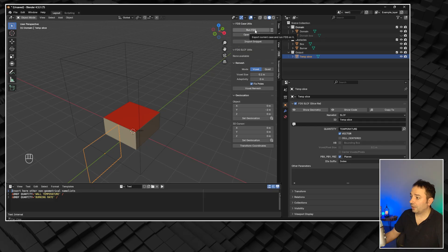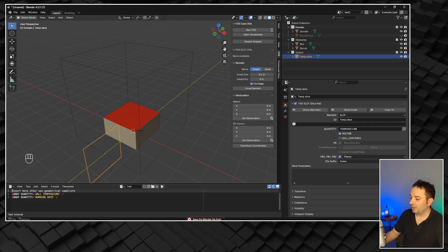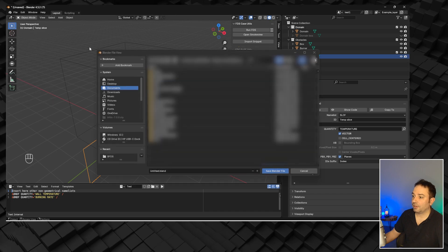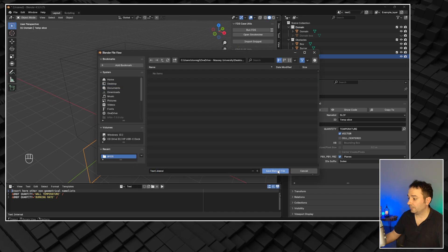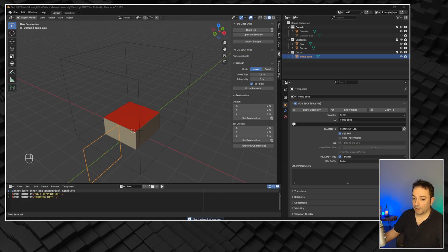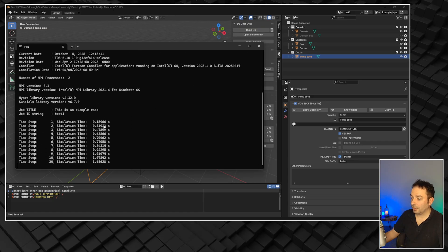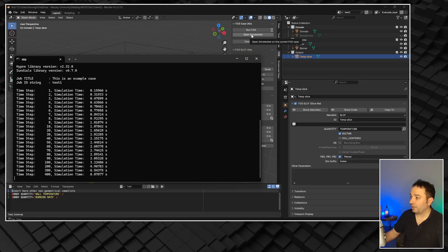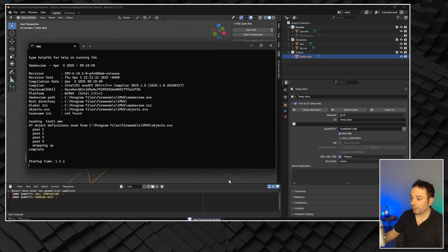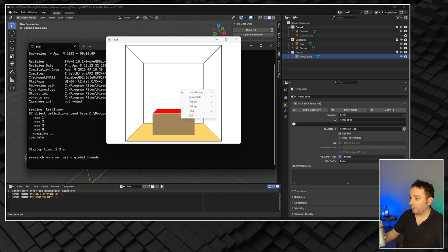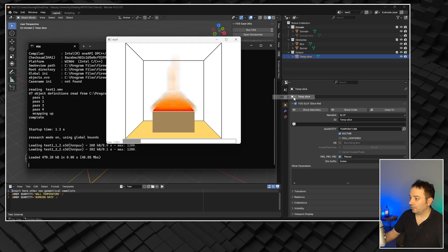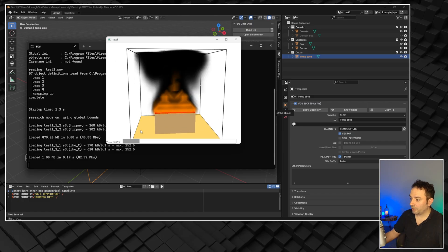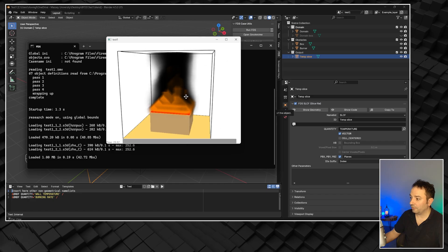Let's go and run it. If you press "Run FDS," you'll get a warning that the Blender file needs to be saved first. So I'm going to save this scenario as "test one." Now we can run FDS, and you'll see that the FDS file is going to open and the simulation starts. We set the simulation for 60 seconds. While it's simulating, we can open SmokeView and have a look — right-clicking in SmokeView lets us see the visualization of the flame and smoke. We can see we've streamed 20 seconds of simulation while FDS is still running.